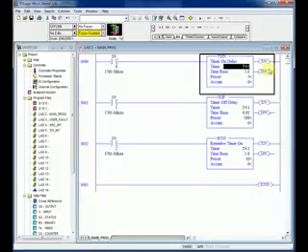These are the three timers. This is enable, and this is a done bit. The done bit will be activated after your delay that you want in TON and RTO. In TOF, the done bit will be activated when the input will go off to on, but will turn off as per its property, after delay of 5 seconds. Let's see how it works.